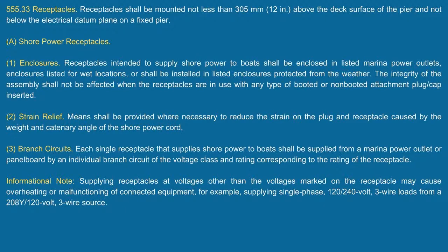And that's when you're cord-and-plug connecting. So when they're clarifying some of these individual branch circuits, they're basically taking it from the definition of a branch circuit and telling you, you've got to have a receptacle there. Otherwise they don't mention receptacle, because you're connecting to utilization equipment, which is hardwired.